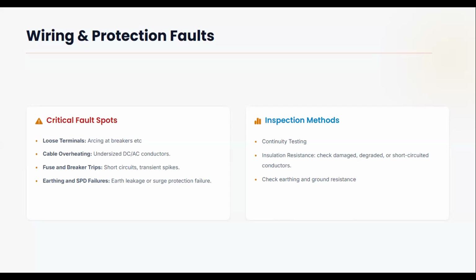If cables are degraded or exposed, for instance using cables that are not ultraviolet friendly, when they are exposed to weather conditions, sun and rain, they tend to crack. The insulation will crack off, and then the conductor inside can be exposed. That's where your client will call you that the roof is shocking. Anything can happen. For such a breakdown on the cable, the best solution is to replace those cables with the appropriate standard and good quality. There are UV cables out there that can withstand exposure, but it's still not good to expose cable like that on the roof.